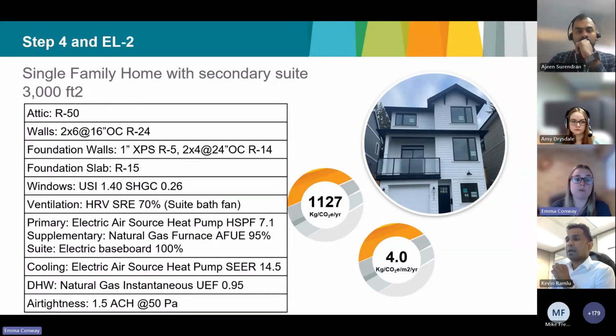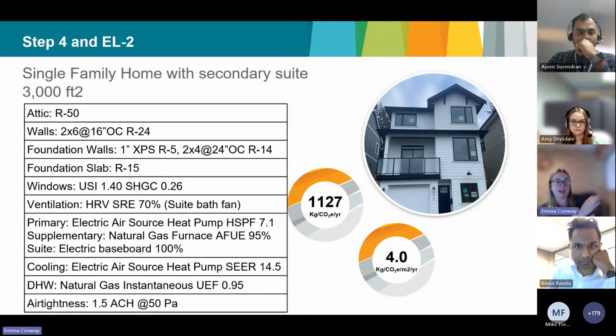Windows USI 1.4, so this is still a double pane, either a really bad triple pane or a really good double pane window. I've added an HRV at 70% SRE for the main house, but left the suite as a continuously operating bath fan with no heat recovery there. For the primary heating system, I've done an electric air source heat pump with a supplementary gas furnace, and in the suite, to keep it simple, I said the suite was electric baseboard.